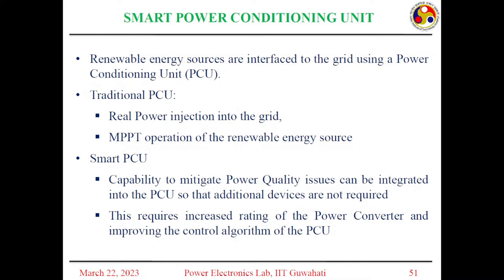If you are using it for additional functionality, we also have to increase the rating of the power converter accordingly. If it is only injecting real power, we decide the current rating of the switches according to the real power injection. But if you have to inject reactive power, you also have to inject some harmonic currents, so for the increased current rating you have to redesign the power converter. With the same design, you cannot use it for both power conditioning purpose and power quality mitigation — you have to design your power converter again. The cost will increase slightly, but if you see the overall cost of using a separate D-STATCOM, it may be better to use the same voltage source inverter as a D-STATCOM.